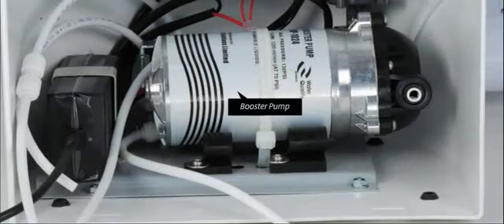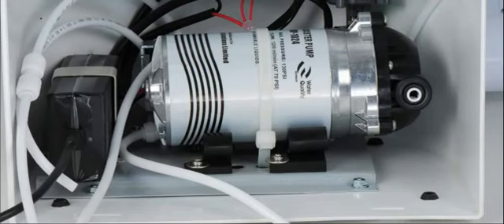This is a booster pump. It is used to provide adequate pressure for efficient membrane functioning. This provides a water flow rate of 1200 milliliters per minute at 70 psi. It works on a 24 volts DC.